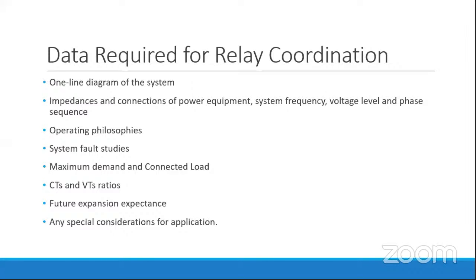Then the maximum load demand and the connected load, such that accordingly we can give settings to our relays. The CT and PT ratios, that is, the current transformer and potential transformer ratios, which are used for the protection and measurement devices. Also, if any future expansion is expected in the network, or any special considerations for any applications are required for their network. These data are required to perform the relay coordination study.